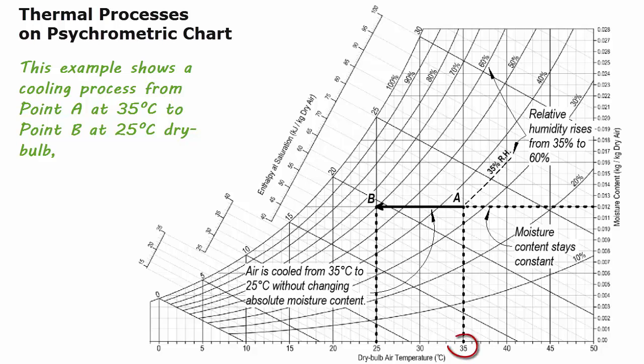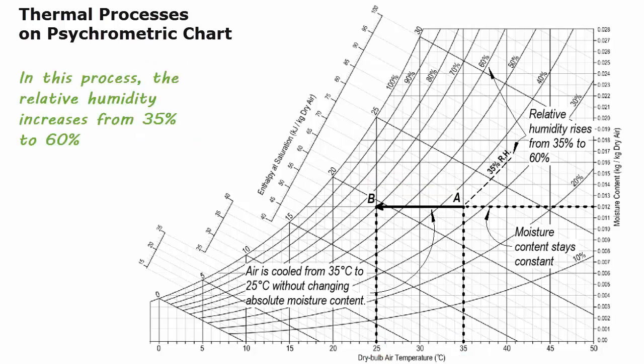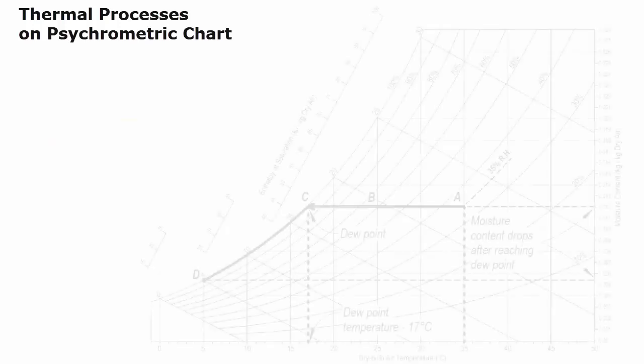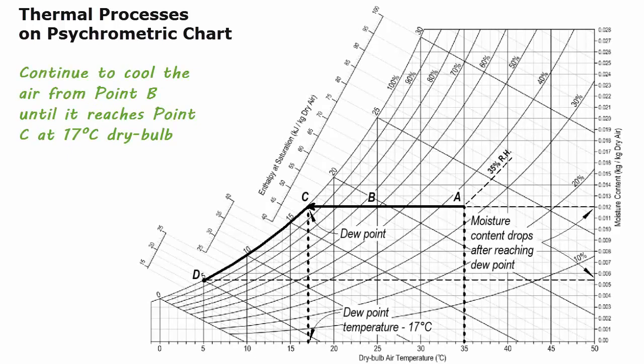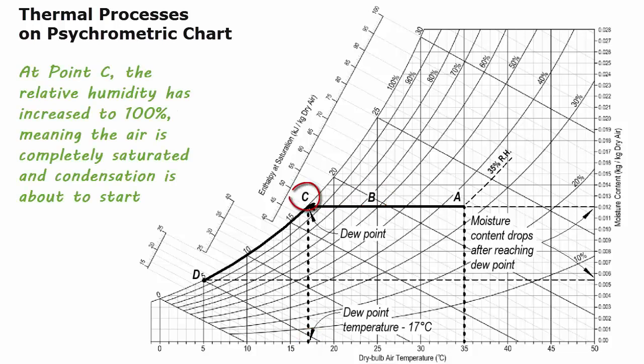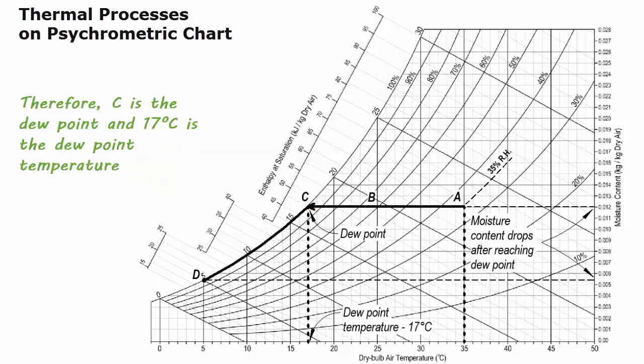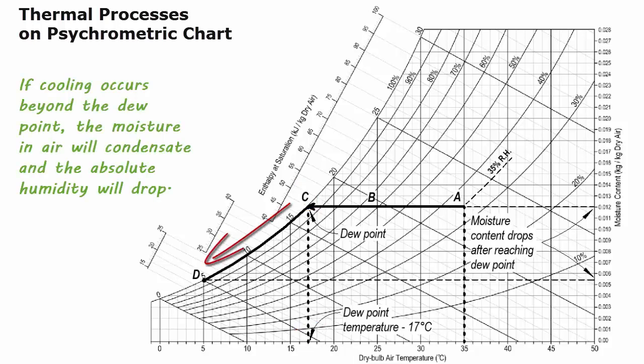This example shows a cooling process from point A at 35 degrees C to point B at 25 degrees C dry bulb. In this process, the relative humidity increases from 35% to 60%. Continuing to cool the air from point B until it reaches point C at 17 degrees C dry bulb, the relative humidity increases to 100%, meaning the air is completely saturated and condensation is about to start. Therefore, C is the dew point and 17 degrees C is the dew point temperature. If cooling occurs beyond the dew point, the moisture in air will condensate and the absolute humidity will drop.